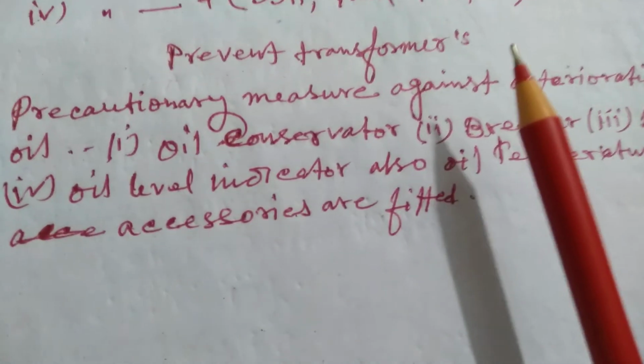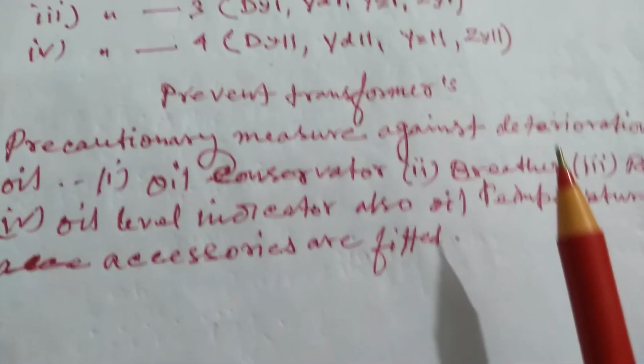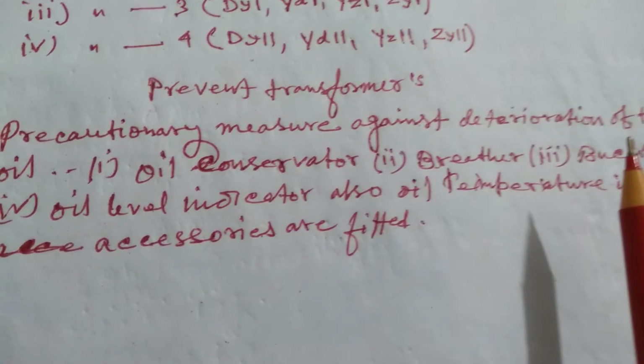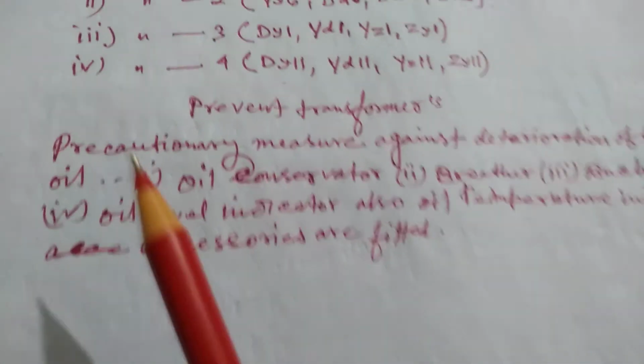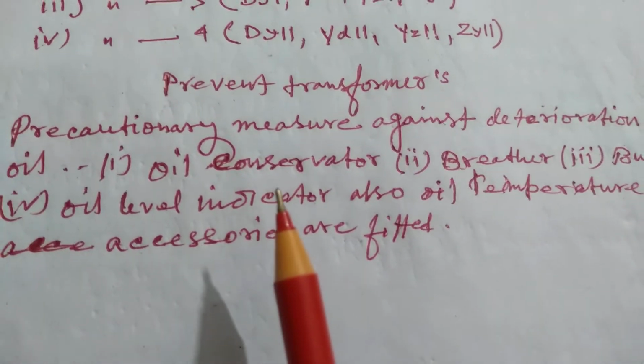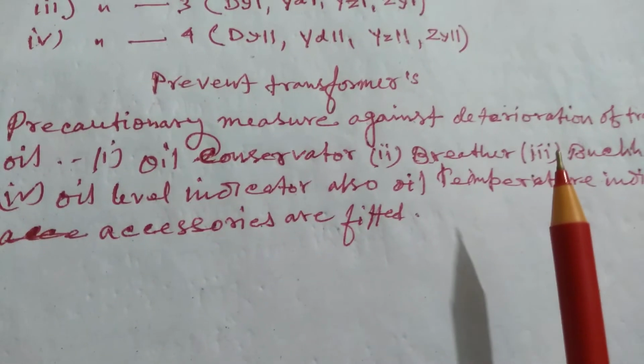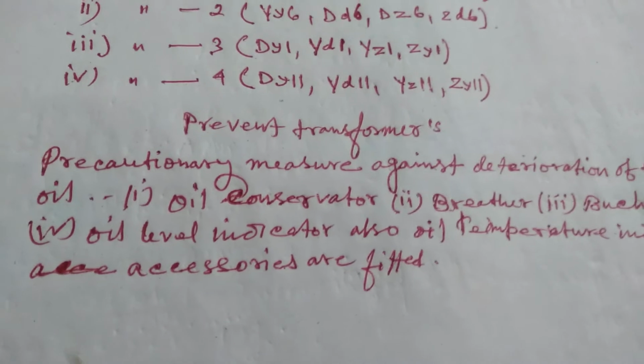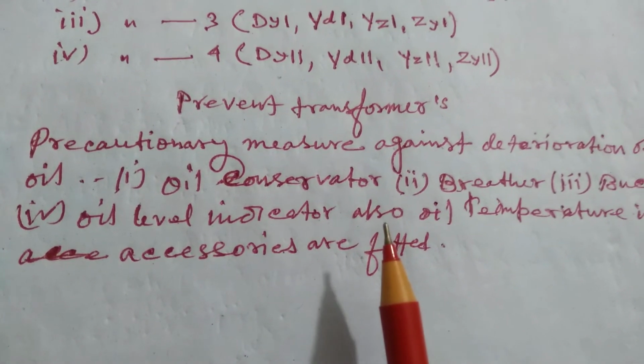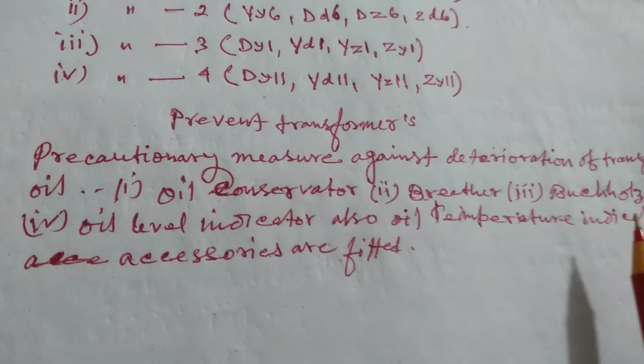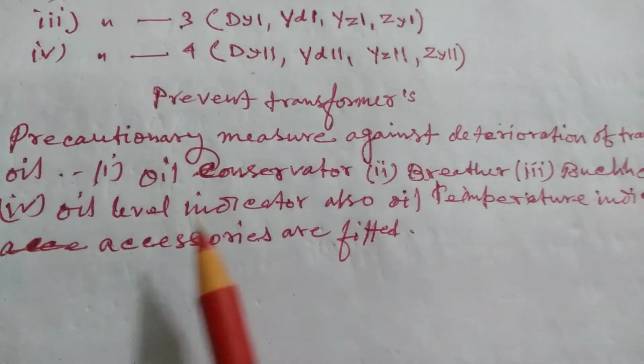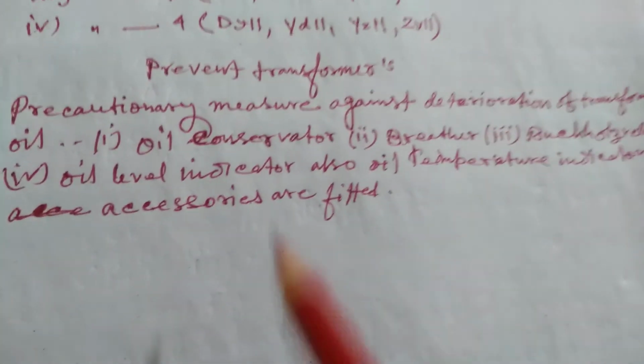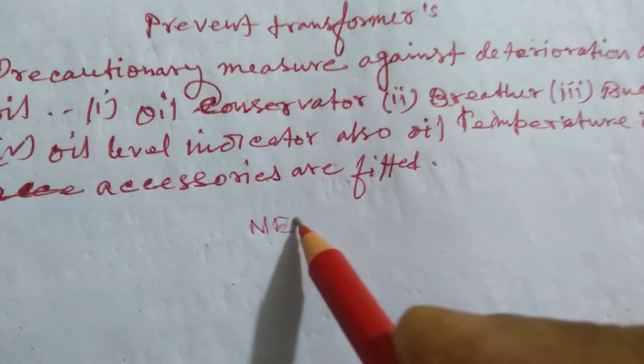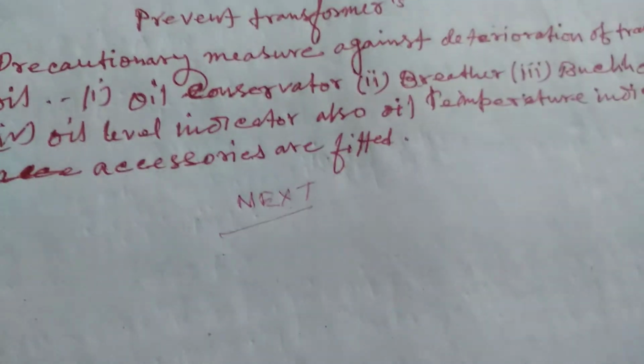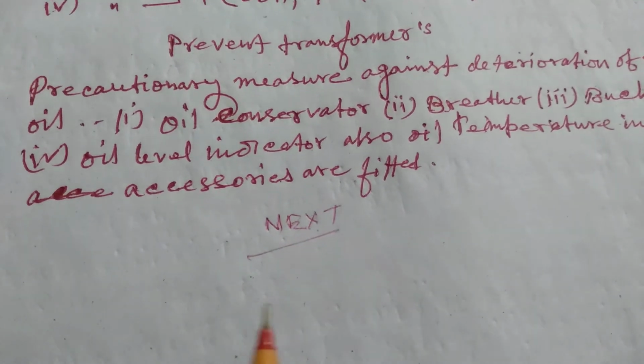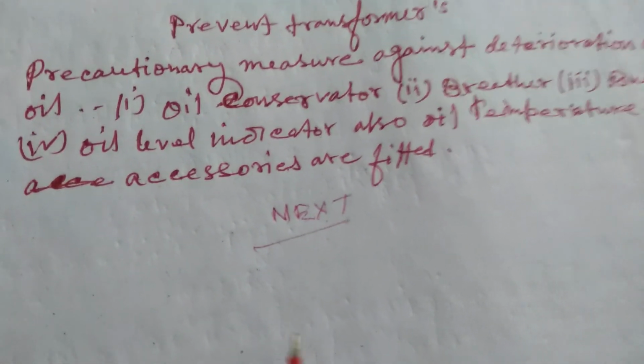Prevention of transformer deterioration: precautionary measures against deterioration of transformers. Oil: number 1, oil conservator tank, breathers, Buchholz relays, oil level indicators, also oil temperature indicators. These accessories are fitted. Next, accessories measures to be analyzed.